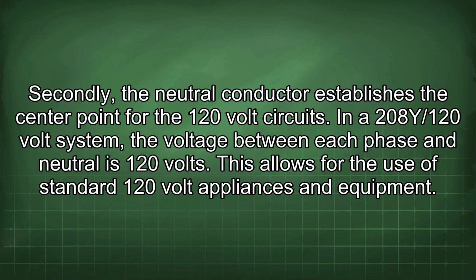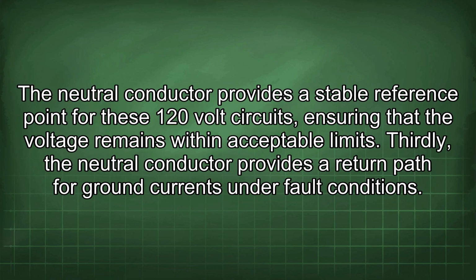Secondly, the neutral conductor establishes the center point for the 120-volt circuits. In a 208Y/120-volt system, the voltage between each phase and neutral is 120 volts. This allows for the use of standard 120-volt appliances and equipment. The neutral conductor provides a stable reference point for these 120-volt circuits, ensuring that the voltage remains within acceptable limits. Thirdly, the neutral conductor provides a return path for ground currents under fault conditions.